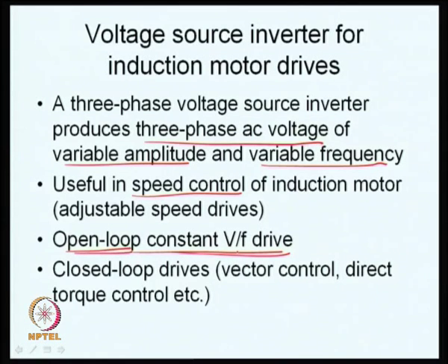This open loop V/f drive is okay when you do not need a very good dynamic performance; its steady state performance is alright. When you want to change from one operating point to another operating point, it is going to take considerable length of time. So, for high dynamic performance you will go for closed loop drives. When you require a very fast dynamic response, you go for a closed loop drive.